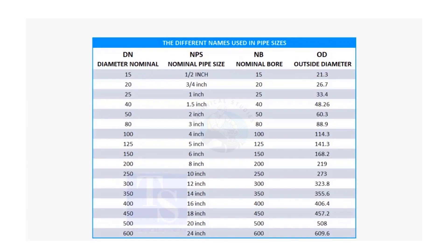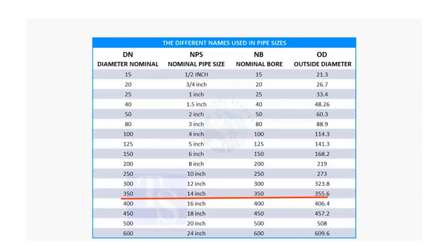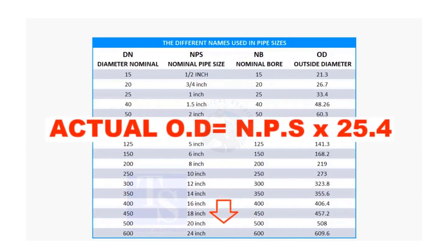In the case of nominal pipe size, the NPS and actual pipe OD are different up to 12 inches. Up to 12 inch pipes, you may need to memorize the actual OD size. For 14 inch and above, multiply the inch size by 25.4 to obtain the actual OD of the pipe.